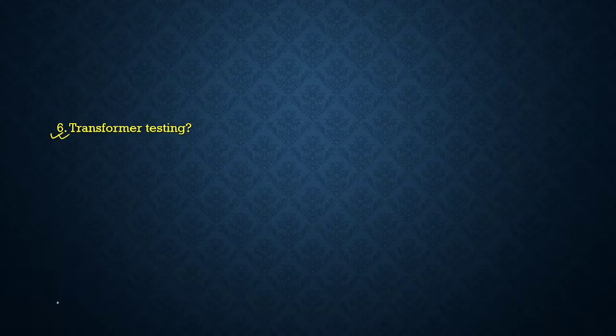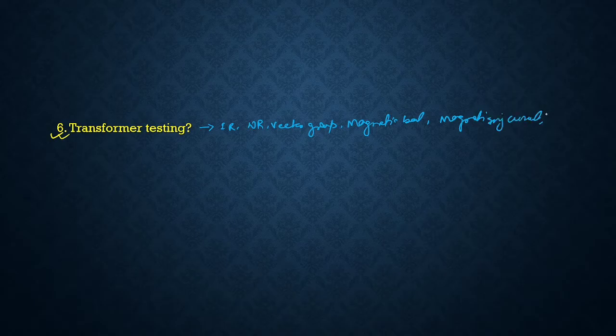The next question was: how do you test a transformer? Suppose you have a transformer, what are the basic tests you performed on it? If you have knowledge of commissioning a transformer, then you will have a basic idea about testing. We take the insulation resistance value, then check winding resistance, then perform the vector group test, then the magnetic balance test, then we check the magnetizing current. These are the tests that we normally check.